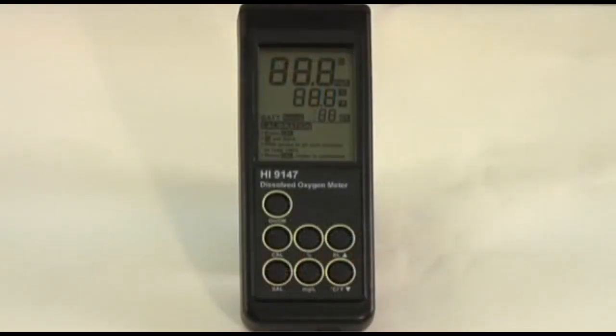Once you've inspected and set up your HI9147, go ahead and turn on the meter. The LCD display will show all of its segments and then indicate the battery life. Since this is a galvanic probe and meter, once the message disappears, you're ready for calibration. Alright, now, let's calibrate. This won't take long at all. It's one simple step involving a 100% water-saturated air calibration.